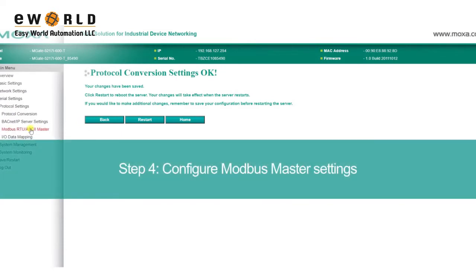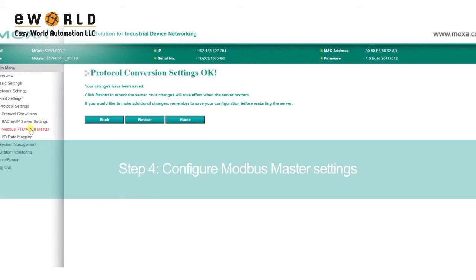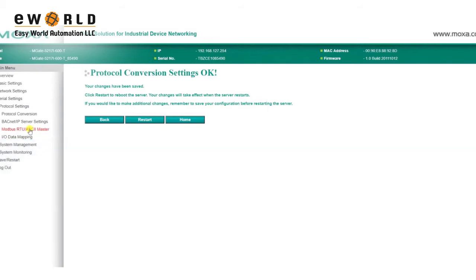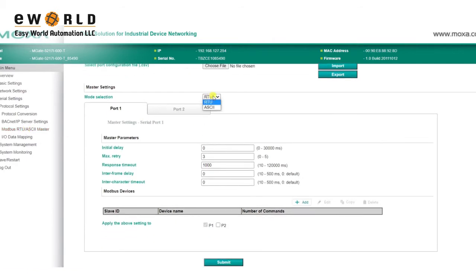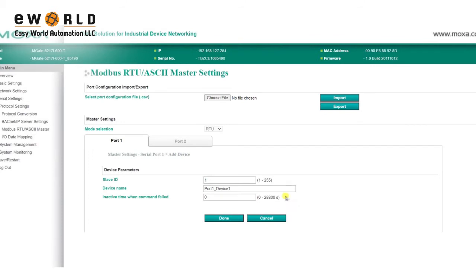Because we selected Modbus RTU ASCII for our protocol, the MGate will act as a Modbus master, and we can configure the related settings by clicking on Modbus RTU ASCII Master. Here, select which Modbus mode will be used. To monitor the power data from the power meter in our demo, we need to click Add to add our Modbus device. Fill in the details as needed, such as the slave ID and the device name to help identify the device, then click Done.